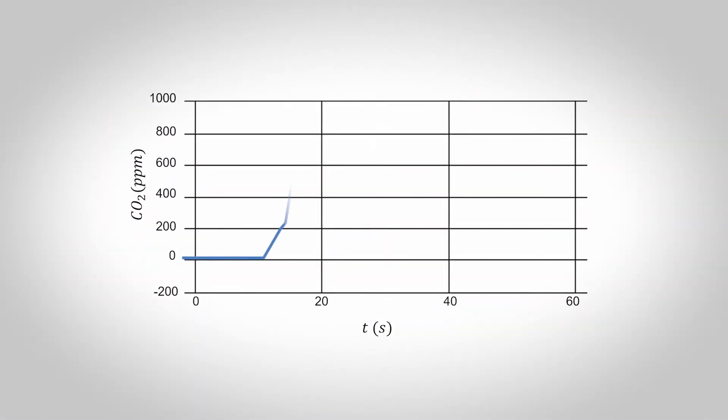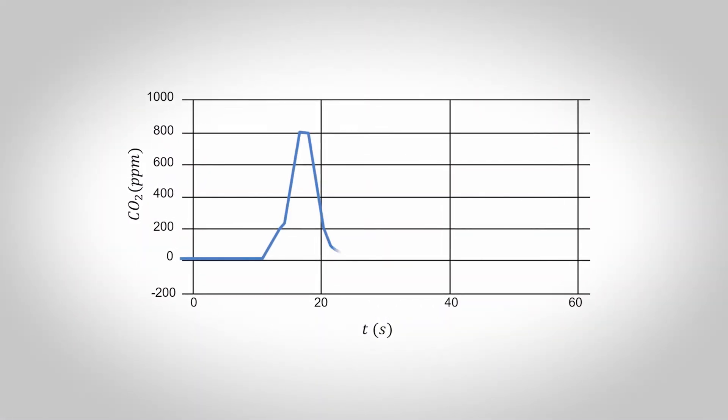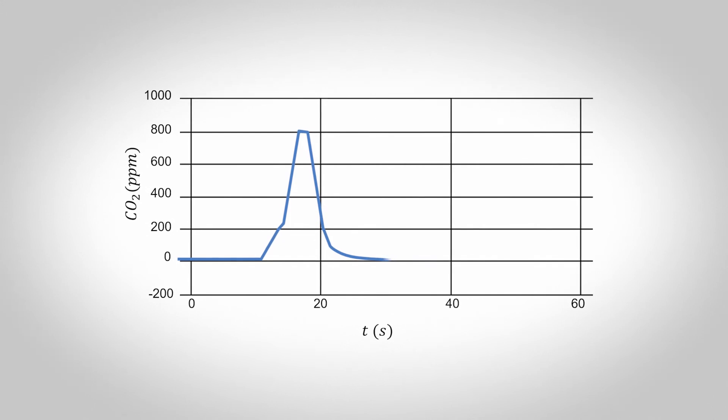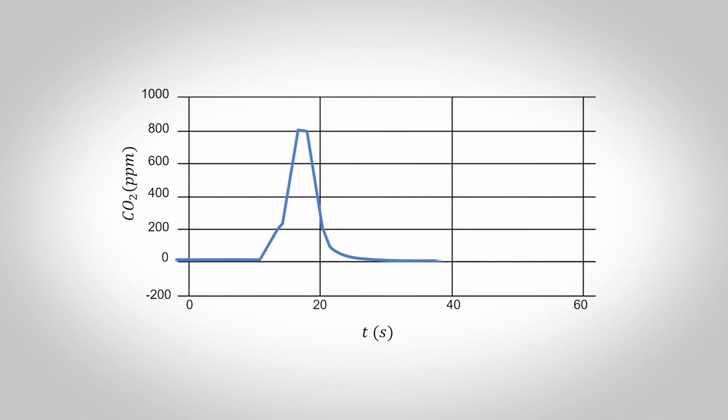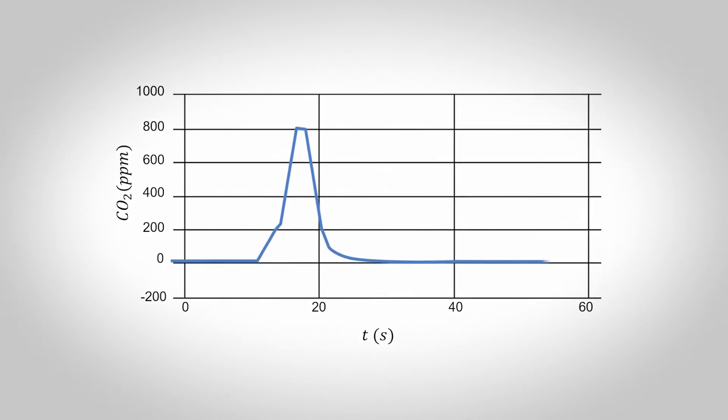The typical CO2 concentration in ambient air is from 400 to 500 ppm. The CO2 pulse from the combustion is typically hundreds to thousands of ppm and is easily measured above the baseline. The integral of the combustion pulse over the baseline represents the total carbon content of the sample.